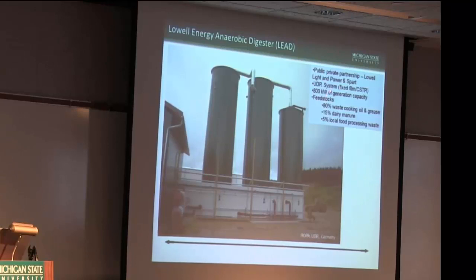The Lowell system is set to produce about 800 kW of electricity, and they're using a very high energy mix of waste cooking oil and grease, as well as a little bit of dairy manure and a little bit of food waste. The dairy manure in this case really is what provides that microbial community. The same microflora in the stomach of a cow is really what's growing in most of these systems. By putting in a little bit of manure every day, you're re-inoculating the system daily. It's not required. You can actually run these without manure at all.